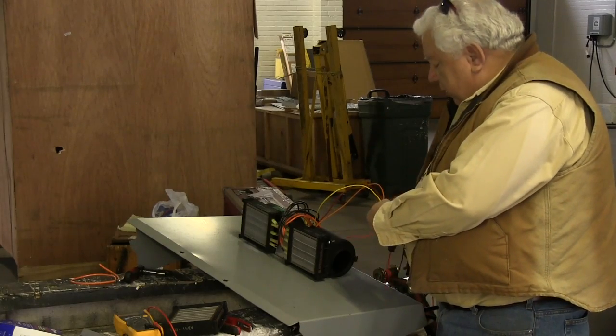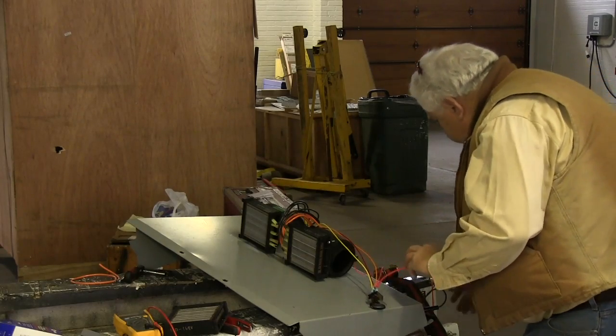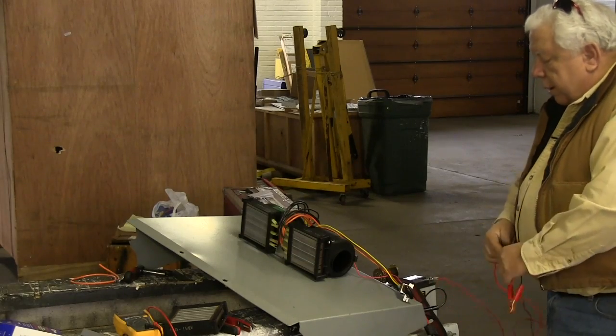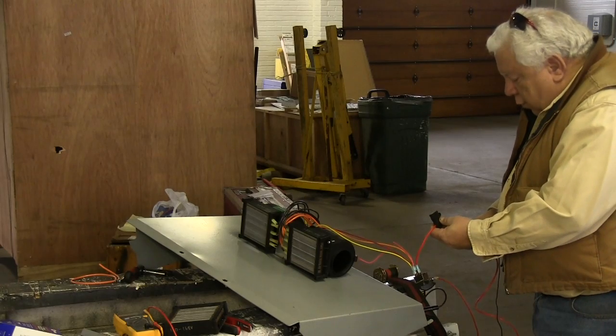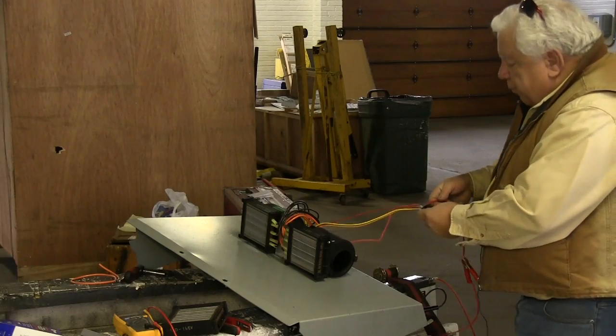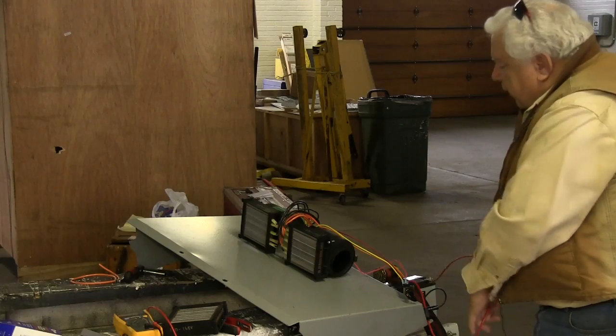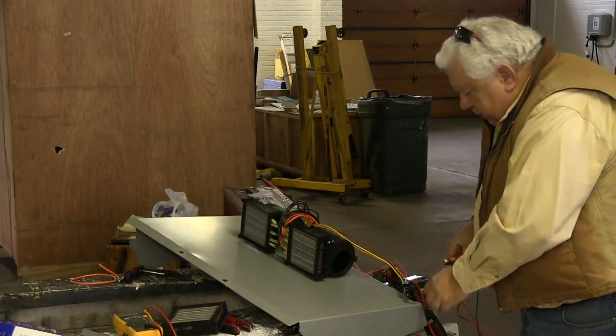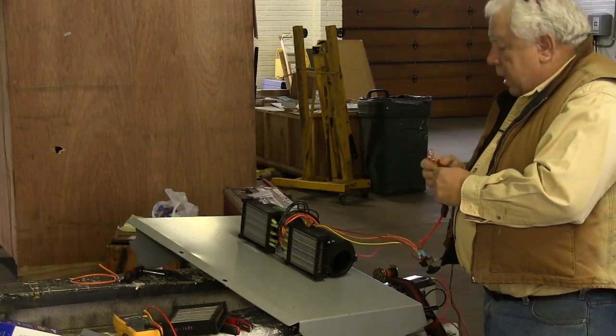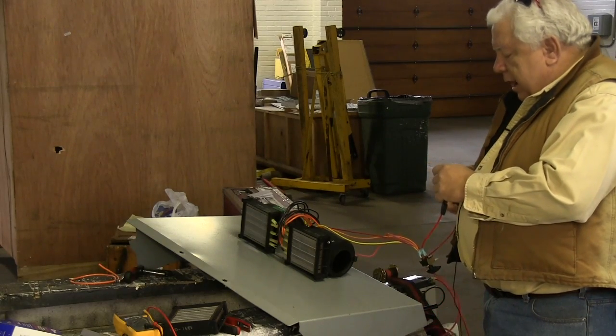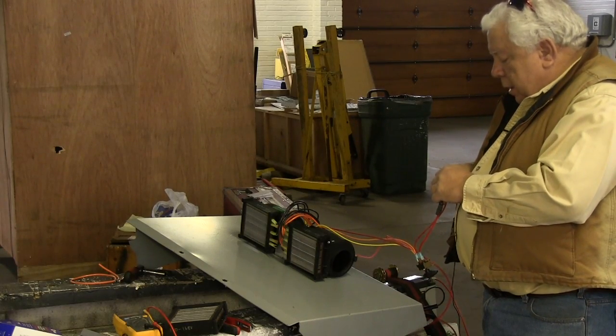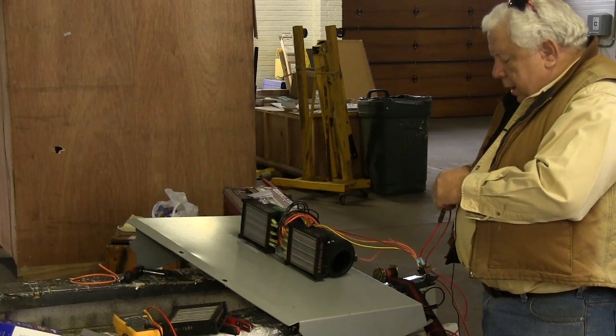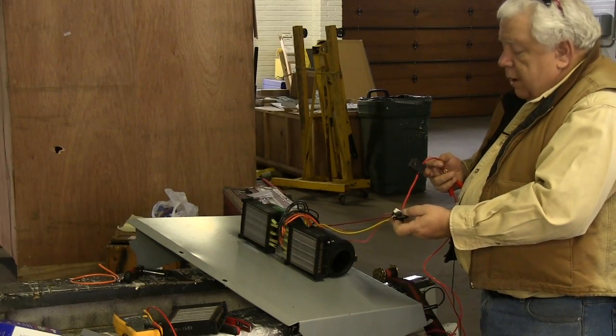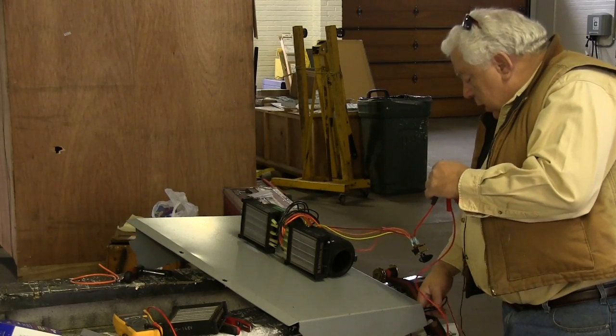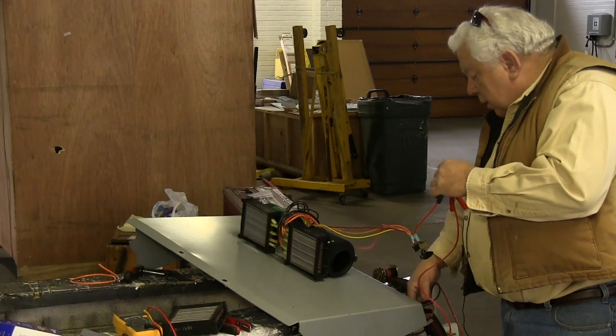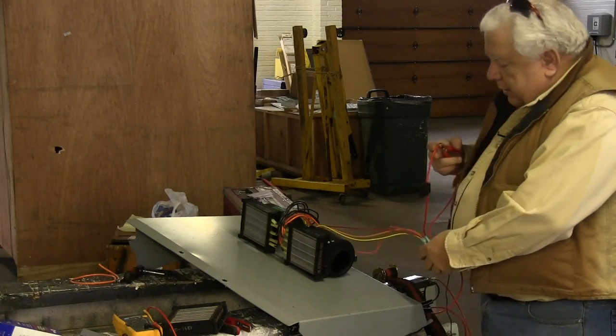Now the fan is a 3-speed fan, and so of course it has 3 wires. I've hooked up a fuse line here to a little 12 volt battery and a 3-position switch. And the way I've got this wired is the contactor is wired to the highest speed. Now this is a little counterintuitive, but the coils in the different windings in the motor for the different speeds are kind of wired together anyway. And so an interesting thing happens in this case. If I can get 12 volt power to it through a fuse, of course, I turn it on low and nothing happens. Here's my ground. I'm using the steel thing as a ground. I get a little whir here, but my contactor does not close.